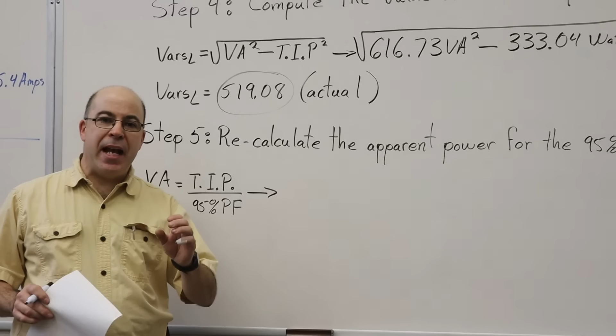Now, this is the next step. We're going to recalculate the value of apparent power, but now for the desired power factor. It's an industry standard to calculate for a power factor of 95%, because as electrical workers we work more in ranges than definite numbers. I could take a reading of an electrical circuit at any point during the day and never see exactly 115 volts. There are always fluctuations, and that's one of the principal reasons we calculate for 95% - it leaves us a little wiggle room for fluctuations in input voltage or line loss.